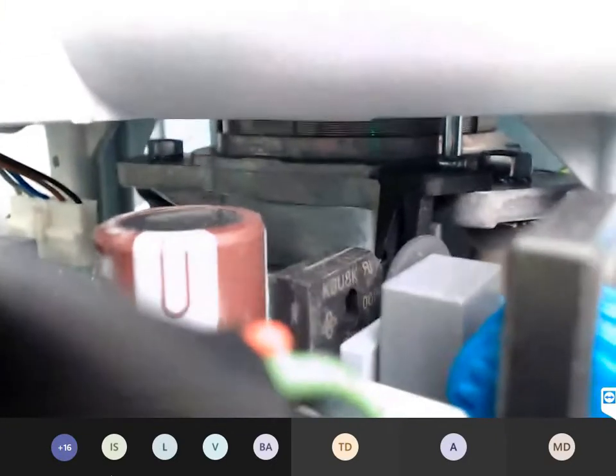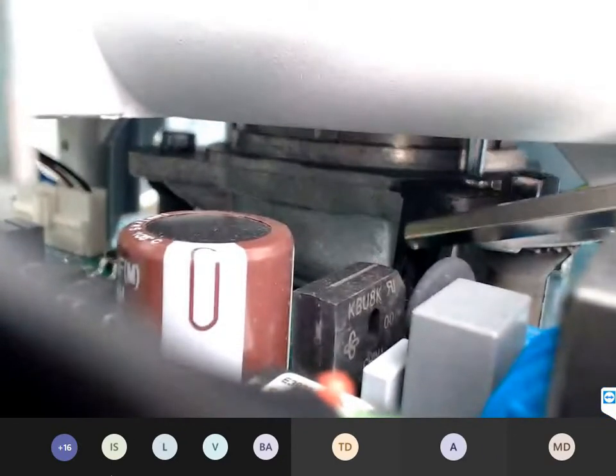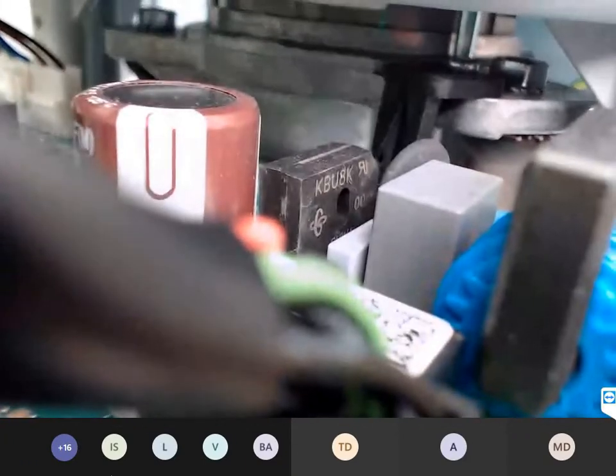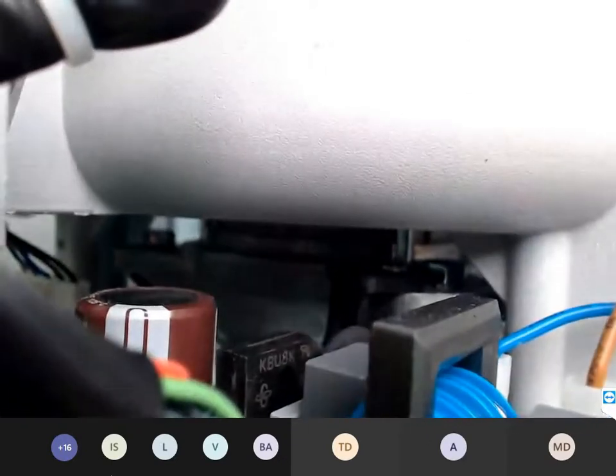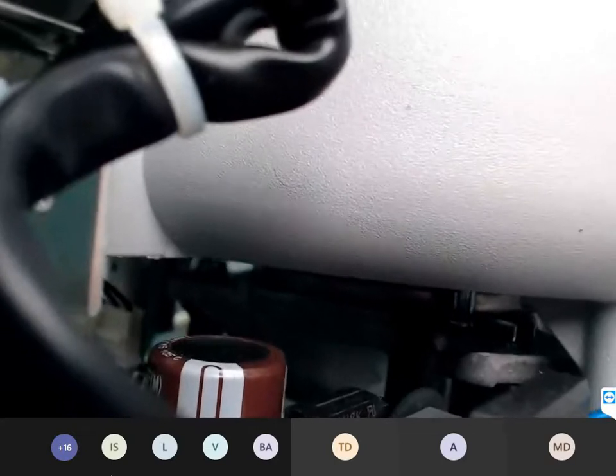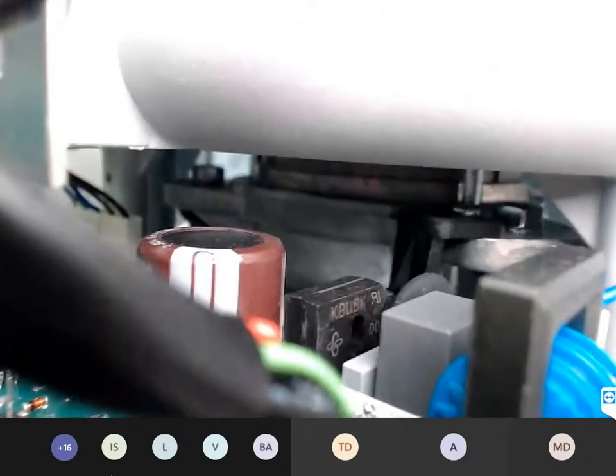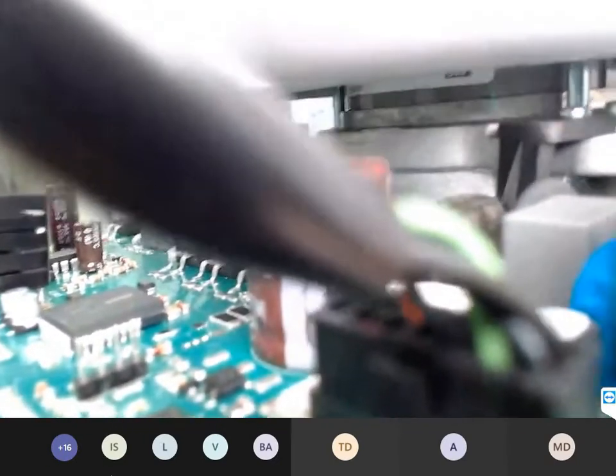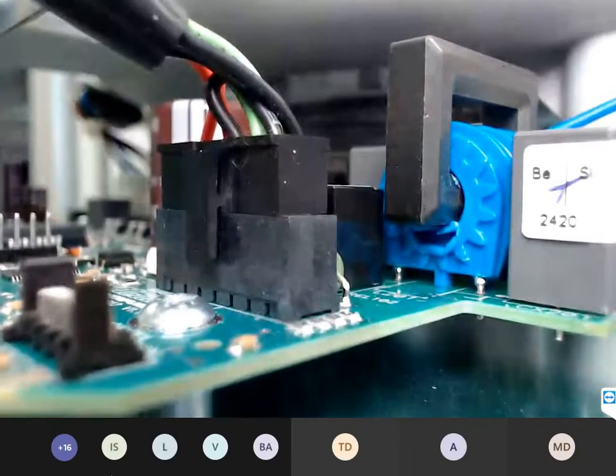This black part on the motor. Just a second. My pencil on my key. This black part here, now you can see it, is the magnet holder with the magnet. This is for the imbalance detection. We have on the electronics a Hall sensor and the device measuring the distance of the electronics to the magnet holder in case of vibration or imbalance. Now you can see the black part. The distance goes higher or goes lower, and then the device recognizes imbalance.